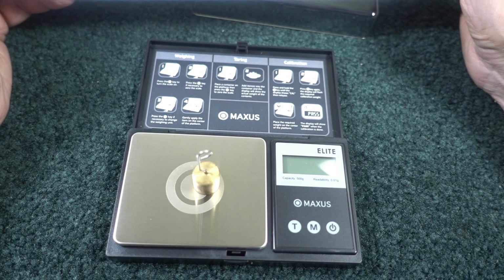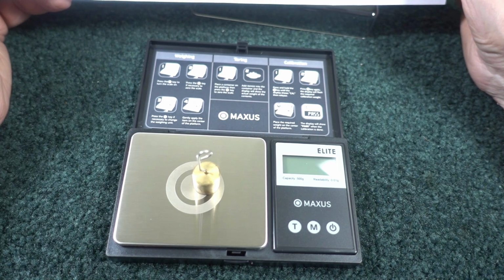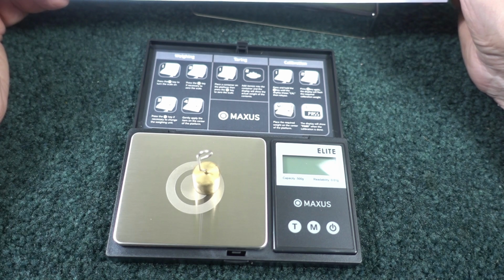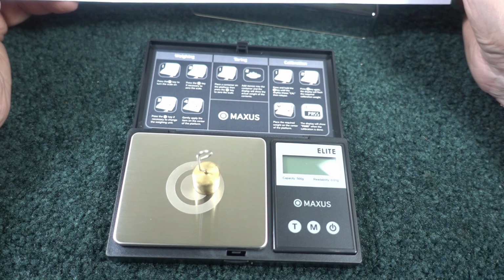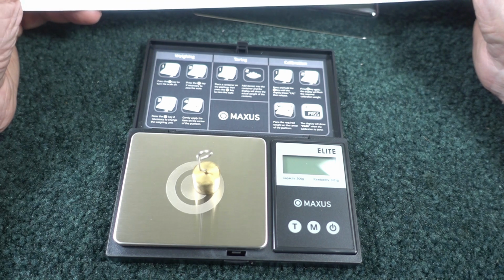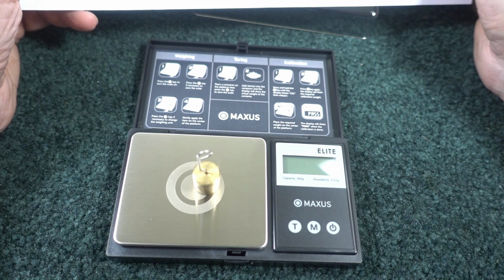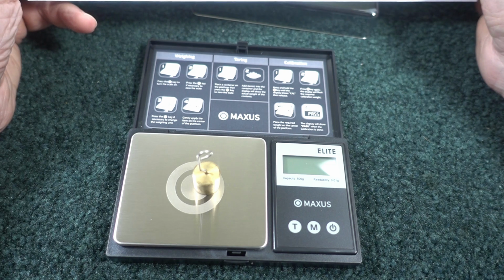There's warning indicators. UNST means the scale is not on a leveled surface. I guess that stands for unstable. LO, low, is for low voltage, replace the batteries. OLD for overload, remove the excess load from the platform. If the scale doesn't turn on, check the batteries or the battery contacts.